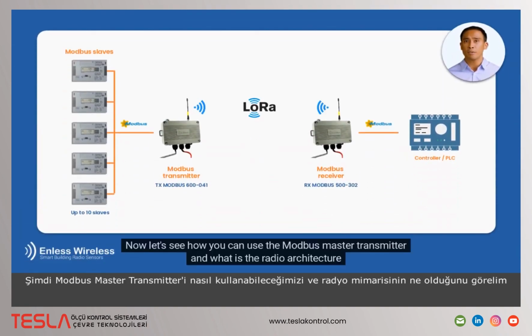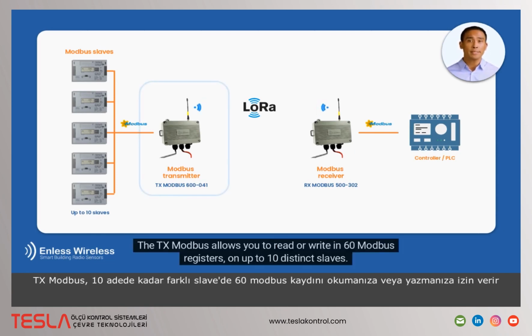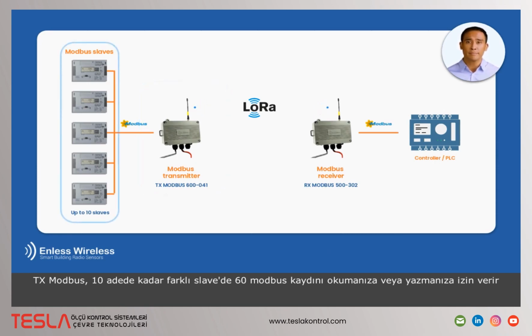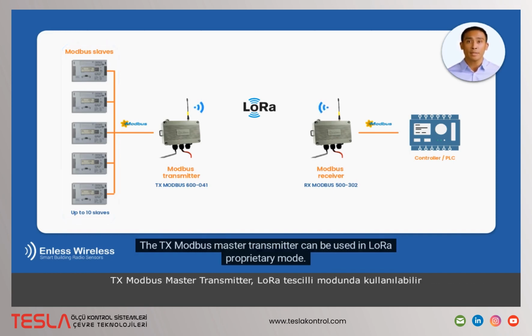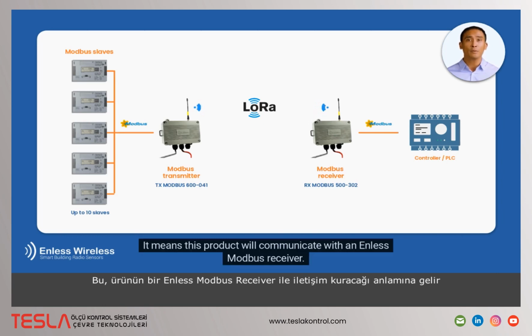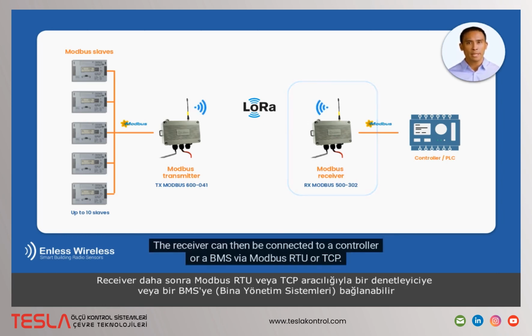Now, let's see how you can use the Modbus Master Transmitter and what the radio architecture is. The TX Modbus allows you to read or write in 60 Modbus registers on up to 10 distinct slaves. The TX Modbus Master Transmitter can be used in LoRa proprietary mode. It means this product will communicate with an Enless Modbus receiver. The receiver can then be connected to a controller or a BMS via Modbus RTU or TCP.